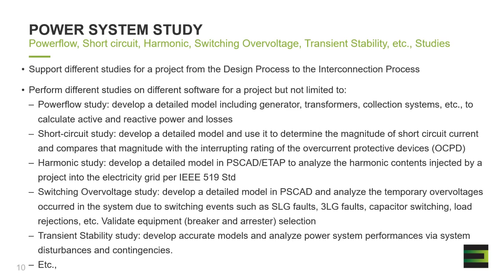this is a growing concern with the more IBR resources we are connecting to the grid. There is a higher harmonic contribution coming out from the projects, and the utilities are taking actions to ensure that the projects do comply with all these requirements. So that includes pre-energization harmonic studies that require a desktop evaluation, and then post-energization harmonic evaluation that requires measuring the actual harmonic contribution coming out of the project site.